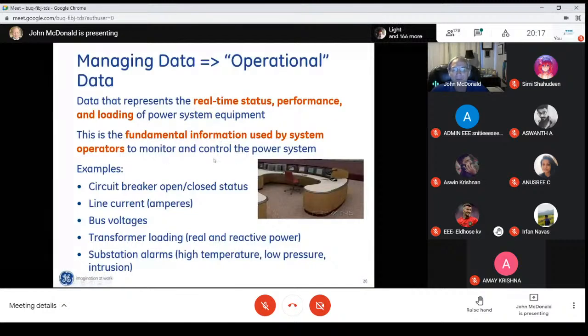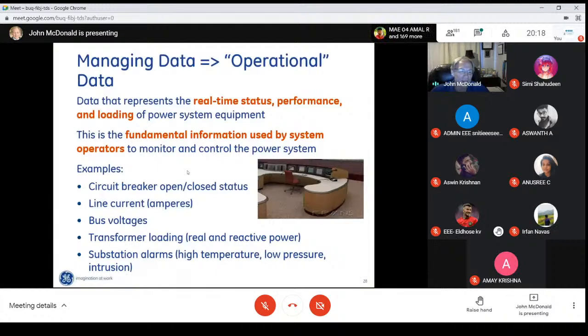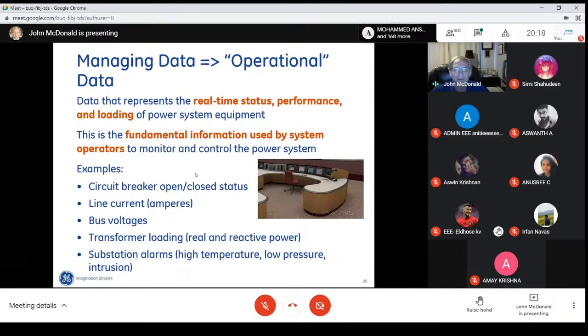Operational data is something that we focused on for many years. It's the information from the field that we send to the control center. So the operators, they know the real-time status, the performance, the loading of the power system equipment. It's the fundamental information used by system operators to monitor and control the power system. And these are points. These are like current, voltage, real and reactive power, circuit breaker open close, alarm information like high temperature, low pressure, intrusion into the substation, stuff. This is all status points or analog points, okay?